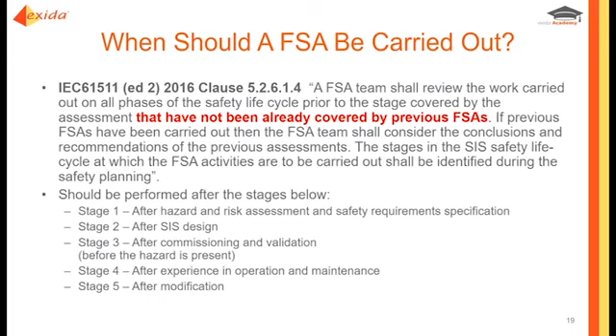And then after modification, we need to do a stage 5. The purpose is to make sure that any modifications are properly assessed from the safety point of view. And if it has an impact or ramification on the SRS, then we have to make sure that the SRS properly reflects any changes. It also says that if you have application logic changes, then all the SIFs that are affected by that application change should also be reassessed. So the functional safety assessments are there to help us manage systematic issues. They should not be missed. Certainly you have to do an FSA 3, but if you do FSA 3, you've still got to cover what FSA 1 and 2 is supposed to do. So you might as well do FSA 1 and 2.